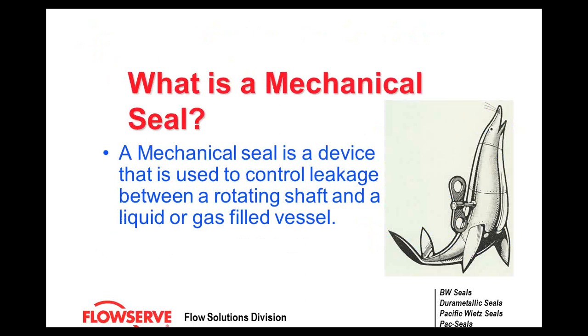What is a mechanical seal? A mechanical seal is a device used to control leakage between a rotating shaft and a liquid- or gas-filled vessel. The key term here is controlled leakage — all seals leak; they have to. You must maintain a fluid film across the entire mechanical seal face. The leakage that comes out to the atmospheric side is generally very very low, often measured with a VOC meter in parts per million.